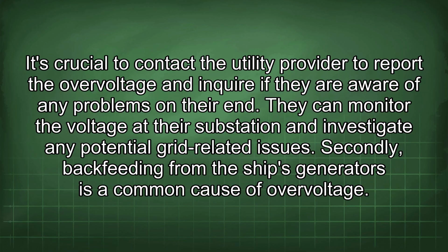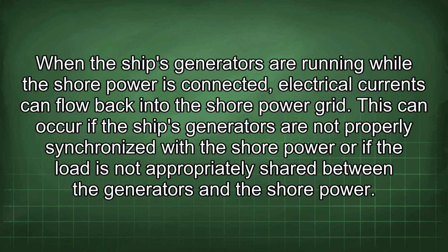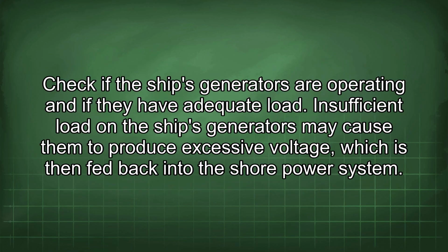Secondly, backfeeding from the ship's generators is a common cause of overvoltage. When the ship's generators are running while the shore power is connected, electrical currents can flow back into the shore power grid. This can occur if the ship's generators are not properly synchronized with the shore power or if the load is not appropriately shared between the generators and the shore power. Check if the ship's generators are operating and if they have adequate load.